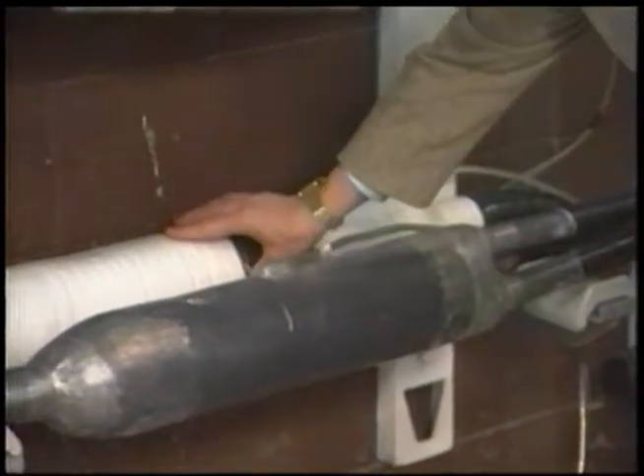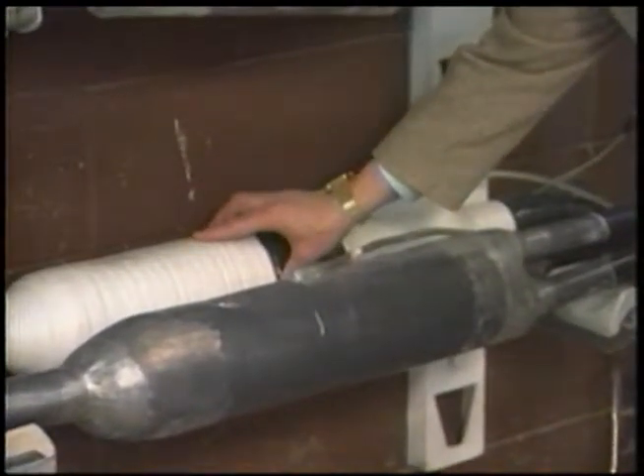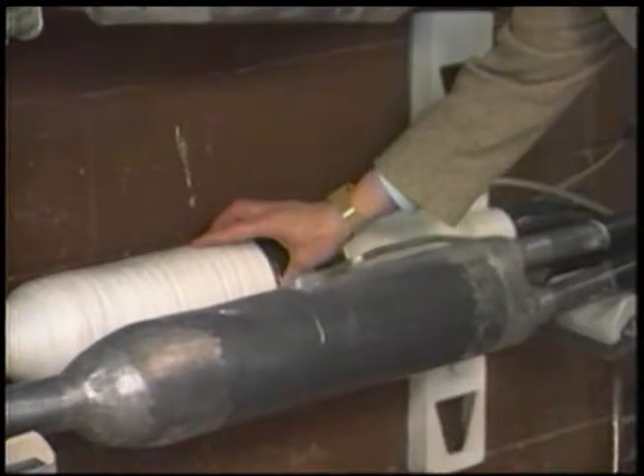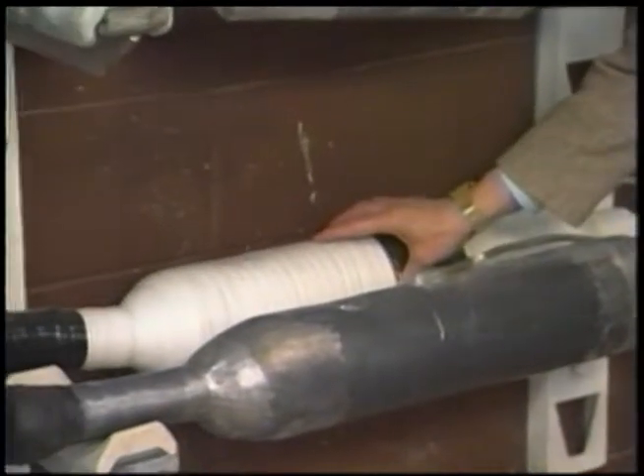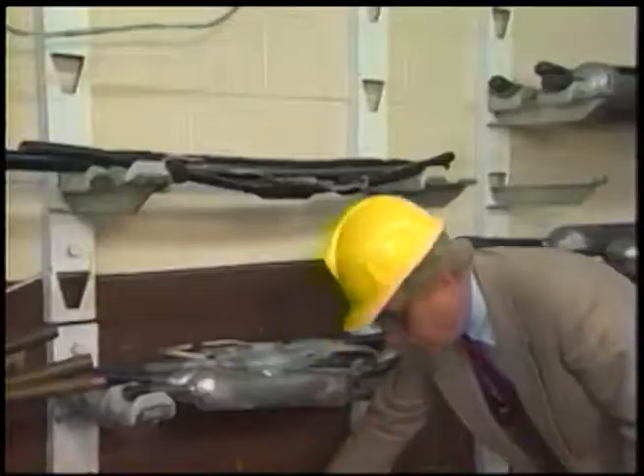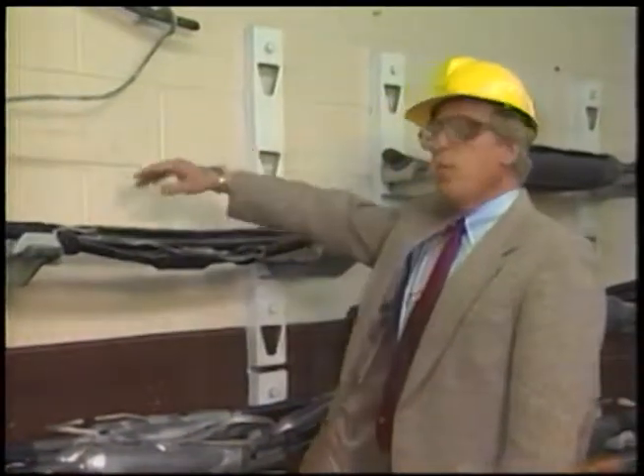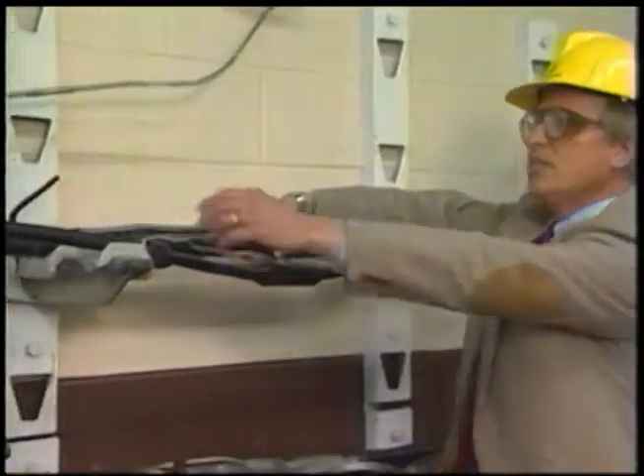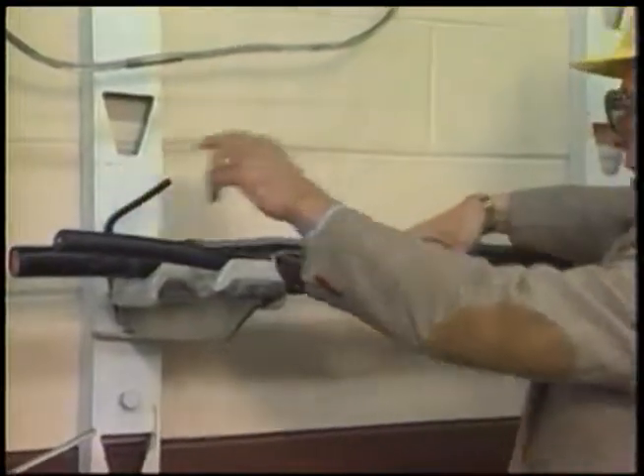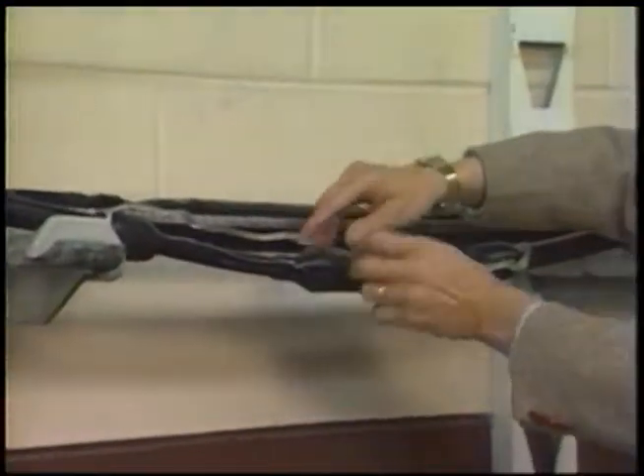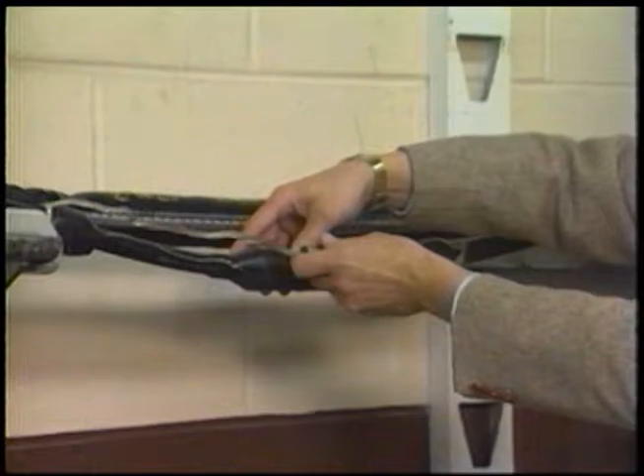Down in the back is a joint made up with arc-proofing tape, and that is to reduce the fault from causing the joint to fail. On the top rack, we have a rubber cable joint. This too has a safety ground that's brought out. In front of it is a plastic cable. It too has its safety ground brought out.